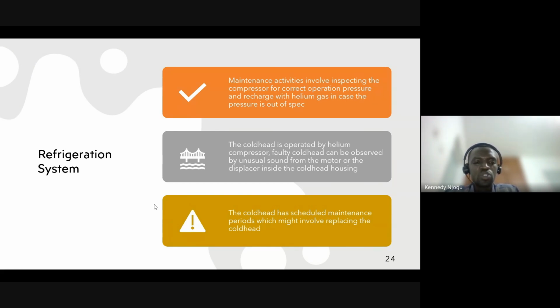So the cold head also has a scheduled maintenance period, as we usually replace it every 4 years. You can replace it based on performance, or for example, you can say 4 years, or based on whether the cold head will fail before the 4 years. But for us, we strictly follow the period when the cold head is supposed to be replaced. Also, we monitor the sound from the cold head. Normally, it has a smooth sound, and if you monitor it regularly, for example daily, you are able to learn the sound produced when the cold head is running. So you'll be able to know if there is something unusual.